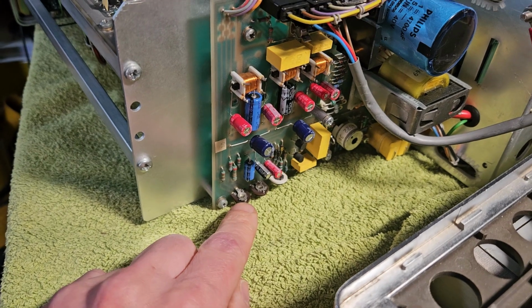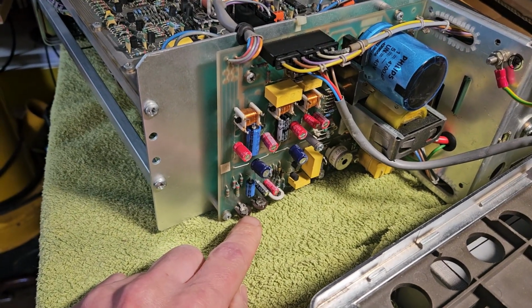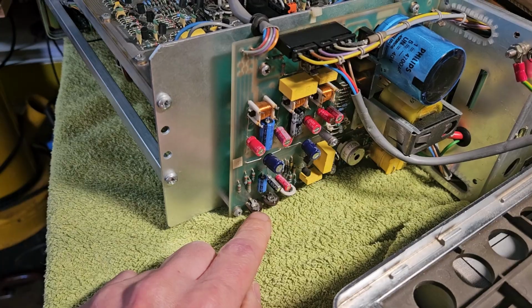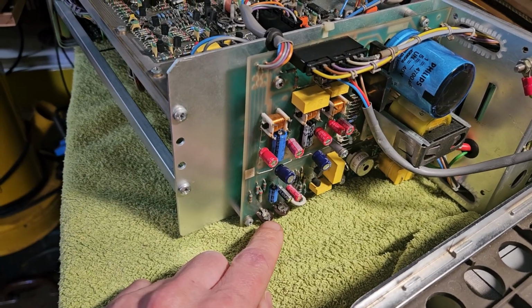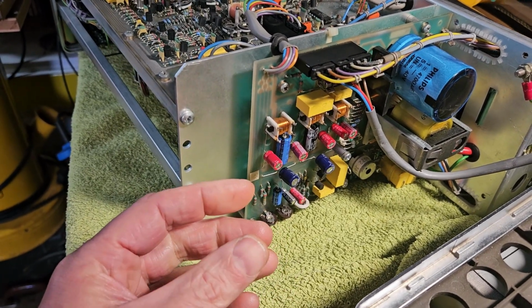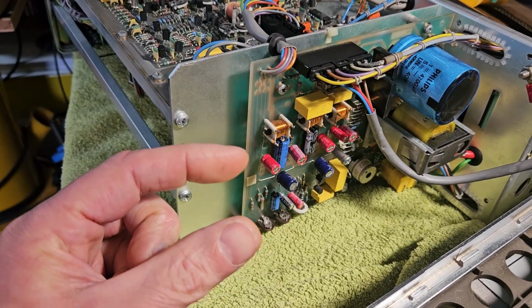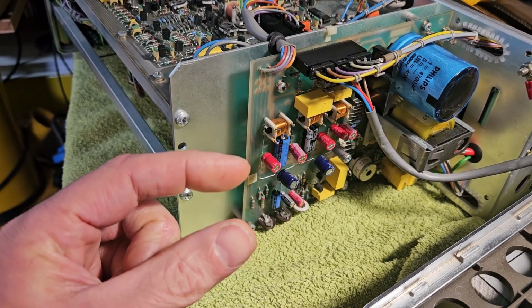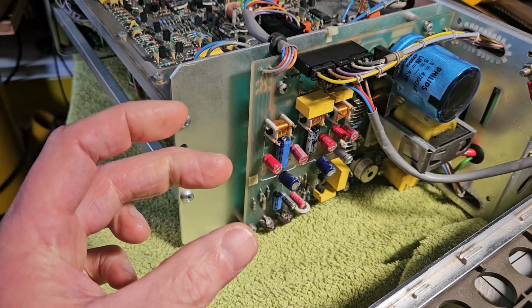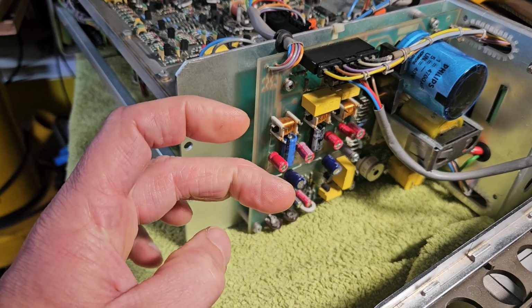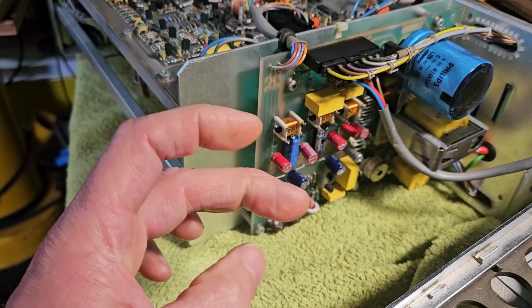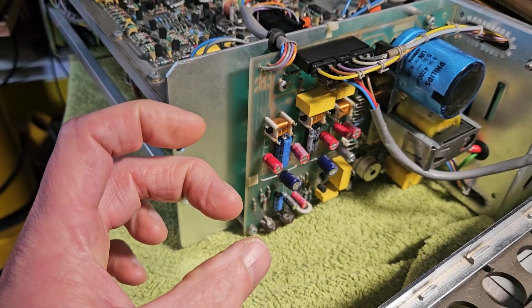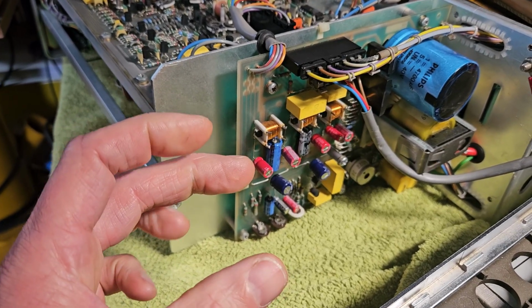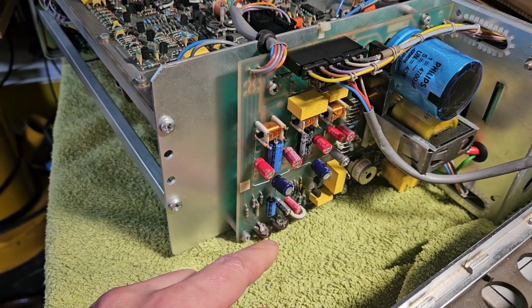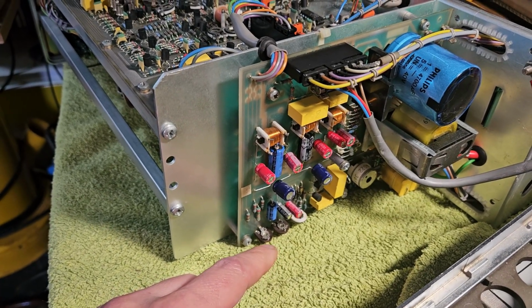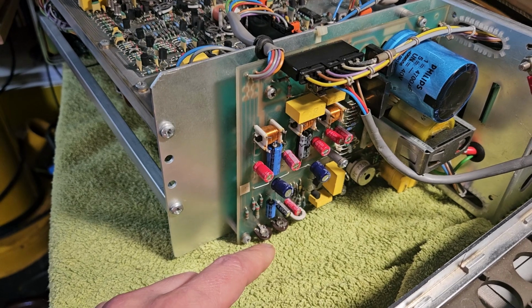This adjustment here on the bottom of the power supply is astigmatism. I'm not going to play with that, I don't think this one needs it, but that is useful if when you're focusing you can't get a progressively smaller circle, if it goes into an oval and then you adjust it further and it goes to an oval the other way. That's the kind of problem you get with a mismatched astigmatism, and so that should adjust that problem, but as I say, I don't think I need to tweak that.